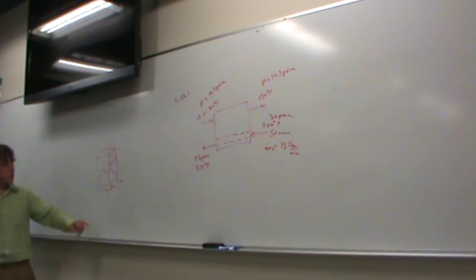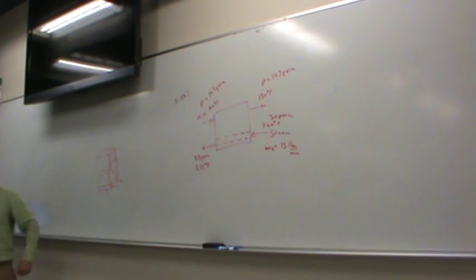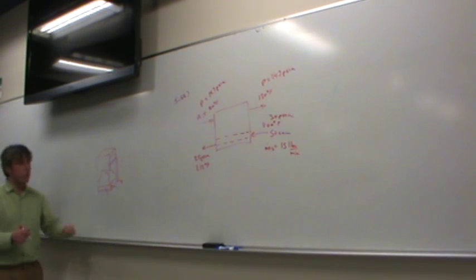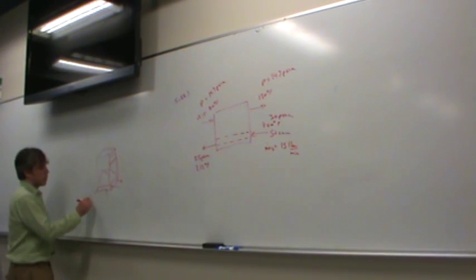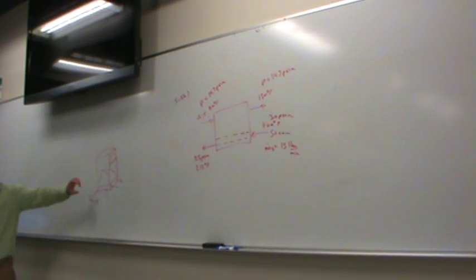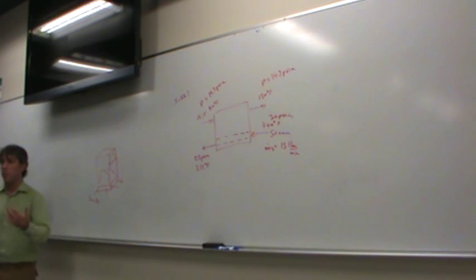Now, during the summer, of course, I'm not going to turn on this coil. But in the wintertime, I turn it on, and in any case, this coil is always mounted here. And so what's kind of interesting about this, relevant to our problem, is the fact that this is called a low DP coil. You don't have to write that down or anything. What that means is it's a low differential pressure coil. In other words, if you look at it, it's a lot more open than most of the heat exchangers.